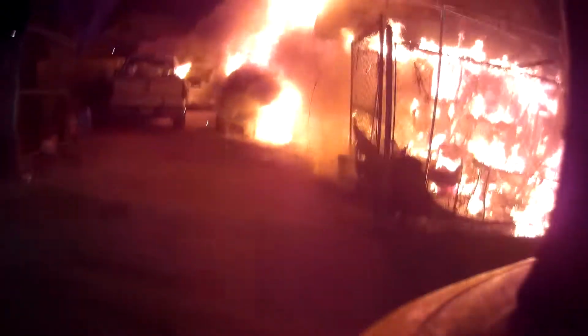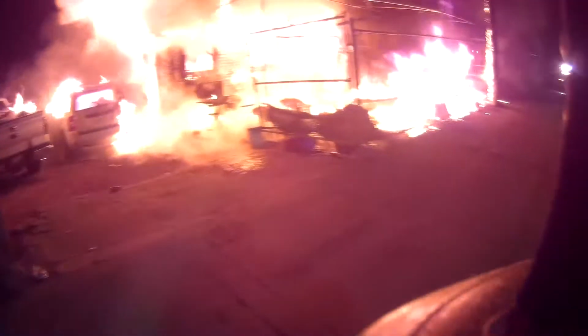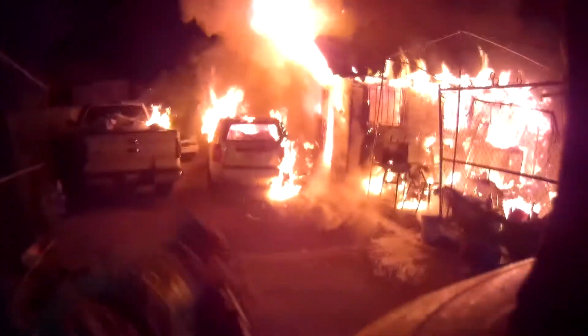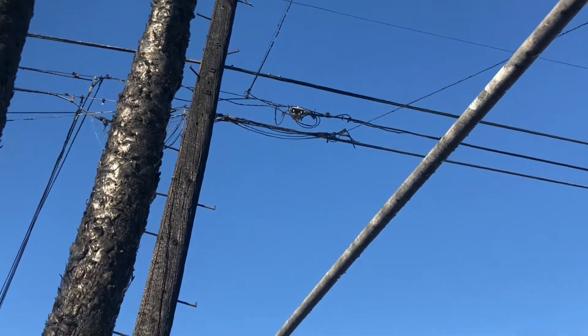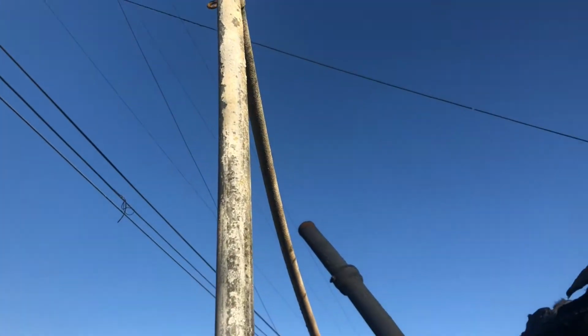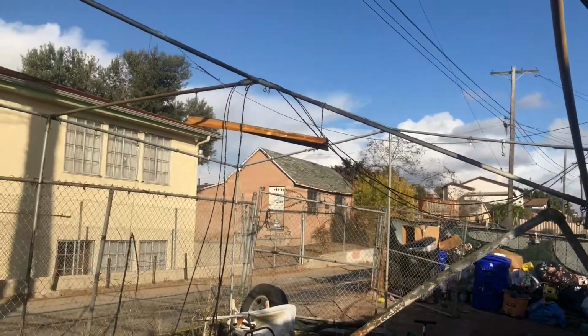Here's his response: the real risk is, if that line goes down and it doesn't trip a transformer or trip the circuit right away, and you have people in close proximity, step potential is your biggest risk. When that line hits the ground, it energizes the ground, the dirt around it, and depending on the load, that determines the range — no one really knows until it's actually happening. But the problem is you get step potential — you take one step into that area, let's say it's a circle, and one foot's in while the other is out. Now you're the path to ground. That's the real scary part of step and ground potential when that line hits the ground.